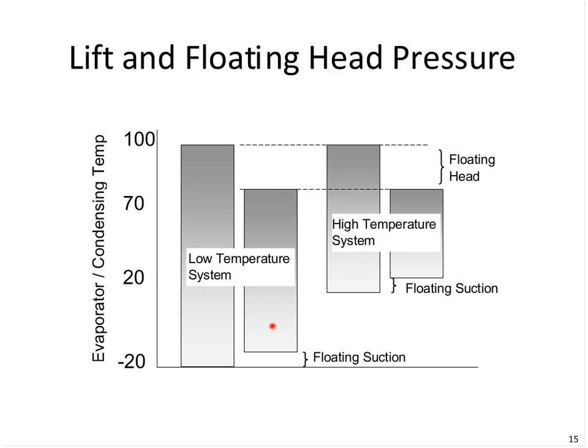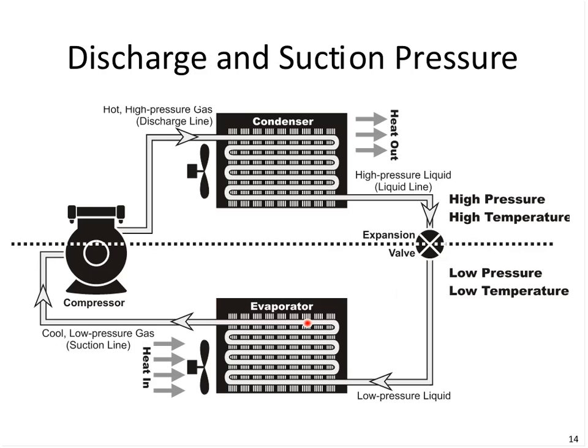So here's the idea of floating the head pressure down, or the discharge pressure, when the ambient allows us to do that, and possibly floating the suction pressure up. We don't need to have our refrigerant at as low a pressure to attain the proper storage temperature. That's known as floating suction. So if I go back a slide here, we're saying, okay, we need a particular temperature here to do the process, but if that lowest temperature isn't always needed, we can adjust this temperature up and still get the job done, known as floating suction.